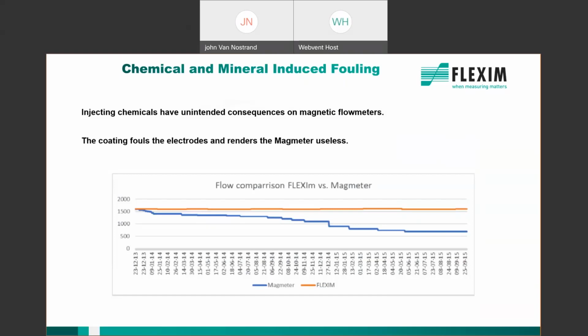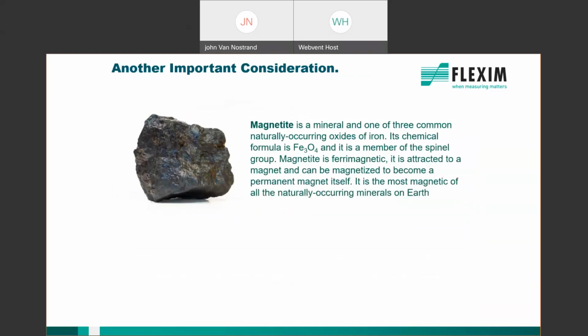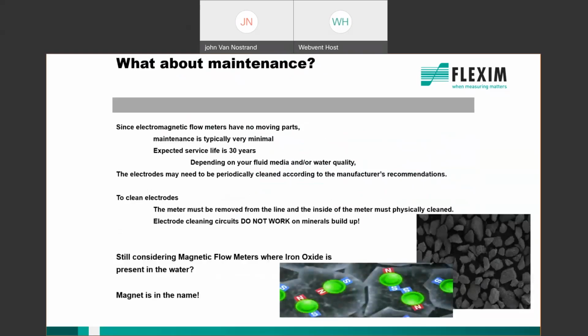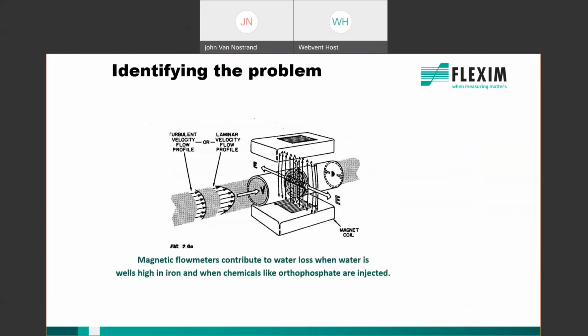In this case, it was, like I said, magnetite, and a lot of people don't realize this, but it's a mineral that is most commonly occurring, and it's attracted to iron. It's basically got its own magnetic force, so it's attracted to any kind of metal, and acts as a permanent magnet onto itself. I'm going to go one more slide here to show you what that looks like under a microscope. On the lower right, you see these little particles. These particles are charged with a north and south pole, and they actually stick to themselves. And what happens on the inside of a magnetic flow meter, I mean, just think about it.